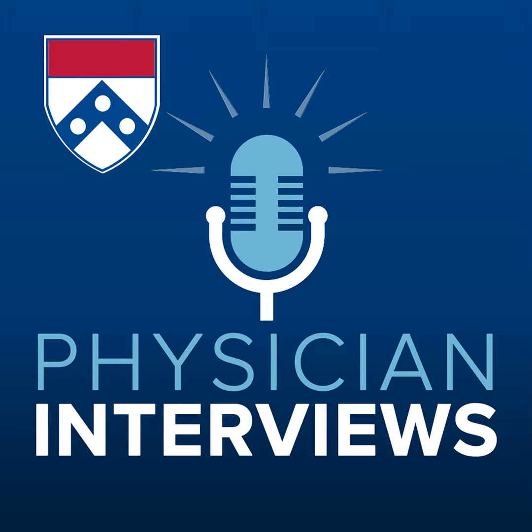It's simplified in the number of energies it has. It's simplified. It doesn't require as much shielding. It's simplified that it doesn't require as much power. And it's simplified that the therapists that run the machine have much less steps to do to deliver the treatment. This actually turns into a much more rapid treatment for patients. So a typical IMRT treatment may take 27 to 30 minutes on a typical linear accelerator, where it takes less than 10 minutes on this machine.